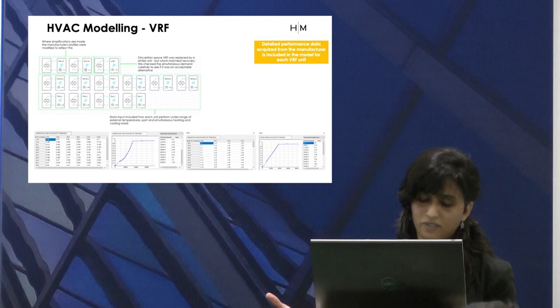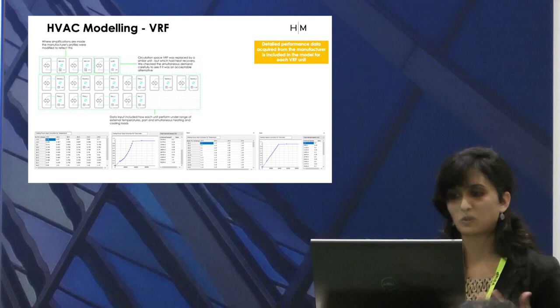So we found an alternative that was matching, but that was a heat recovery unit. So we checked the demand for heating and cooling for the whole year, hourly, to see when the demand is happening simultaneously. We only found 9 instances where that was happening, so we thought it was a good alternative to use.